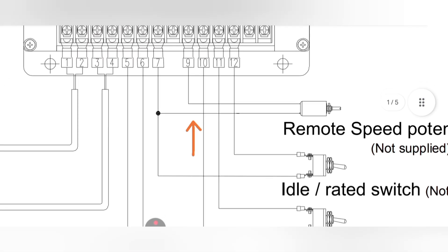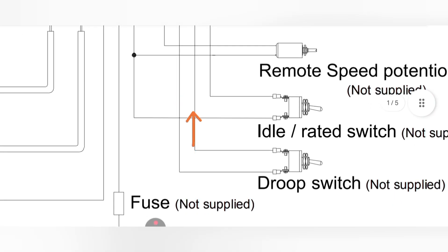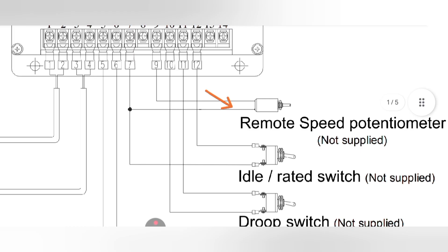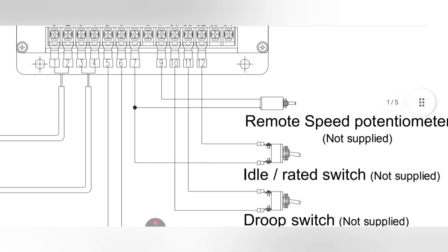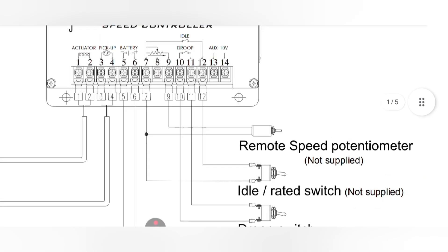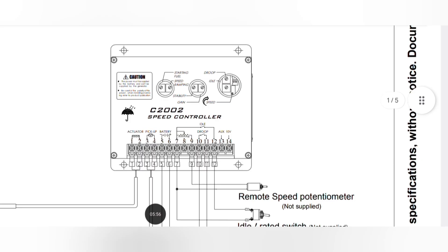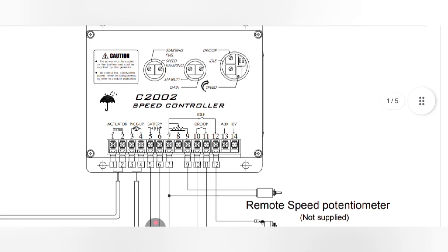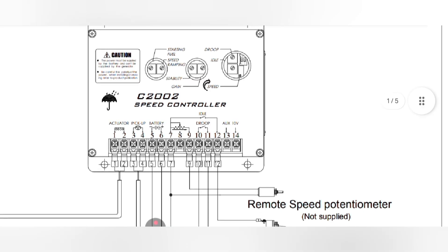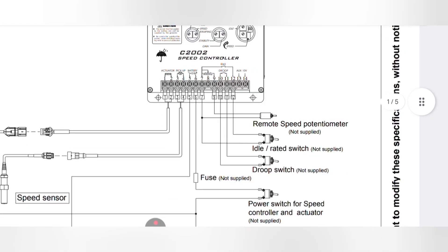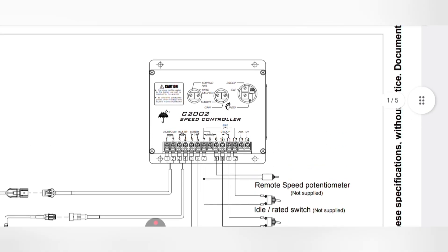Pin number ten and pin number eleven are for the idle-rated switch, controlled manually by toggling the idle speed on and off. Idle speed means a larger generator must first start at a lower RPM — for example, if the rated RPM is 1800, we first run it at around 800 RPM for one to one-and-a-half minutes, then close the toggle switch to let the speed ramp up automatically.